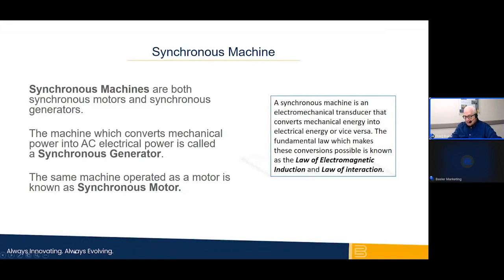The electric machines are, in general, tied to each other by attachment to the bulk electrical system, the utility lines. When attached to the bulk electrical system, these machines share synchronized frequency and common voltage levels as transformed in the interfaces to the utility lines. Electrical machines are mechanisms with a rotating element and a static element. The rotor moves on its axle inside the stator of the machine. The rotation of the rotor is the means by which power is given by the machine or given to the machine. The stator is the interface with the electrical system.